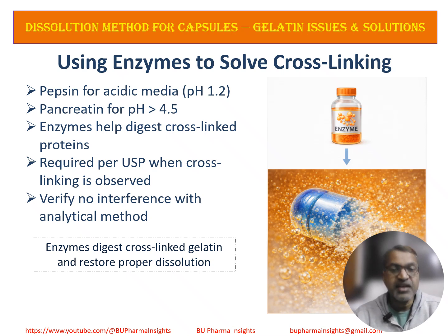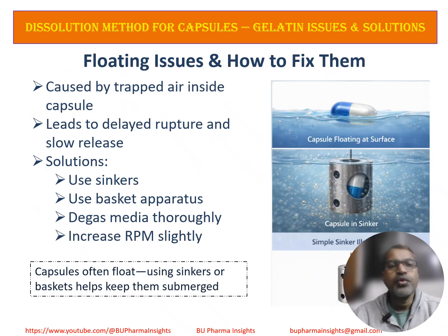Diagnose first, correct scientifically. Floating capsules are a common dissolution problem. This usually happens because of trapped air inside the capsule shell, which prevents proper wetting. The impact: delayed rupture, slow and inconsistent drug release, poor reproducibility.